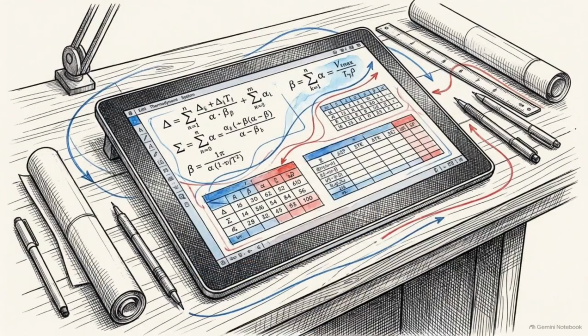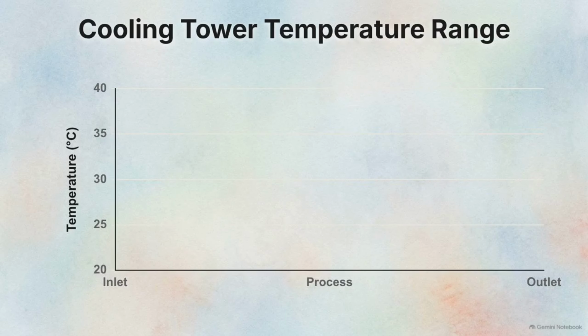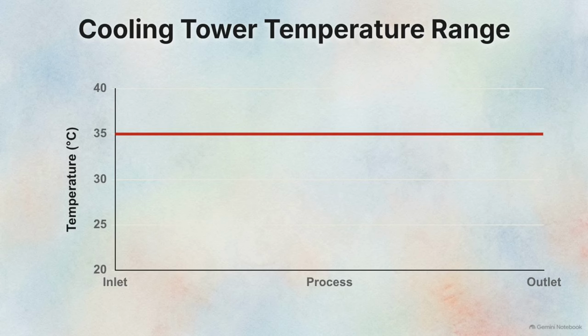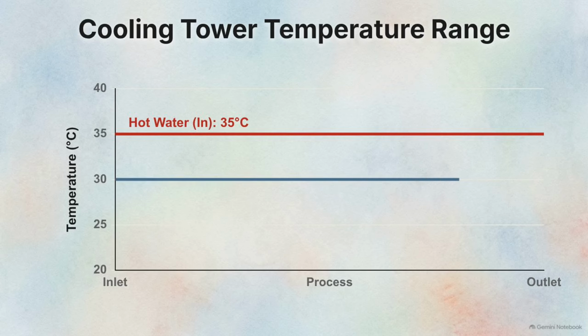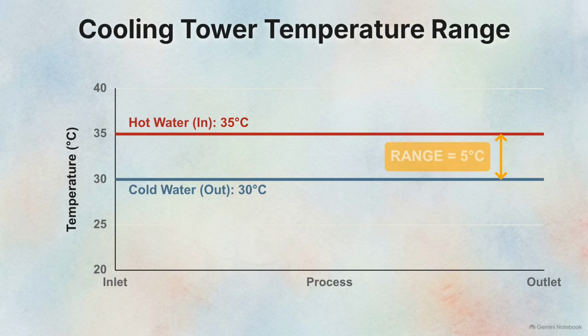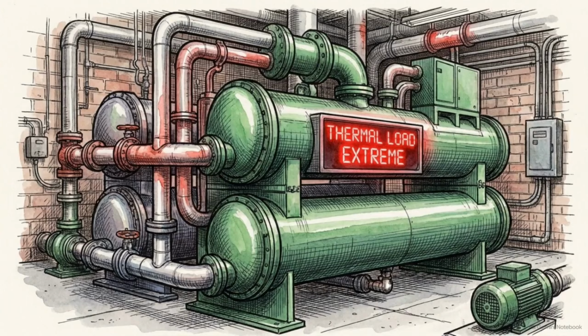To evaluate a cooling tower's actual performance, we rely on exact mathematical metrics to measure the work being done. This chart shows the temperature deltas inside the system. The first variable is the hot condenser water arriving from the chiller. Let's say this enters the tower at 35 degrees Celsius. The second variable is the cold water leaving the basin at 30 degrees Celsius. The absolute difference between these two numbers is the range. In this instance, we have a range of 5 degrees. Range simply represents the thermal load dictated by the chiller.